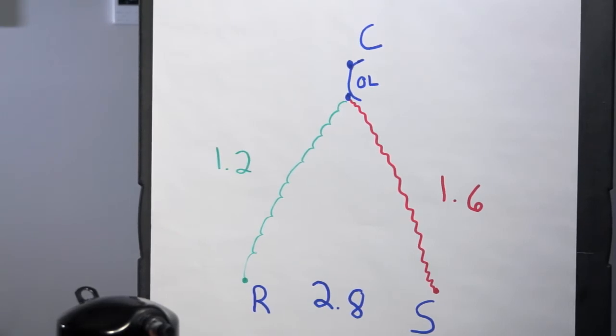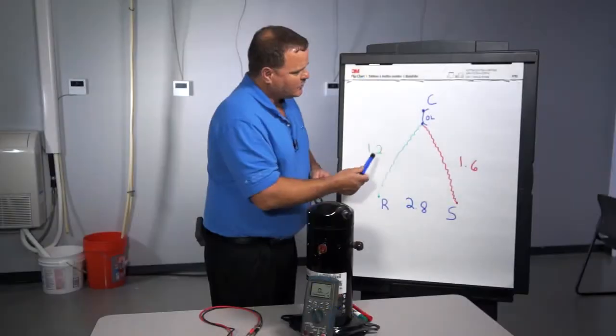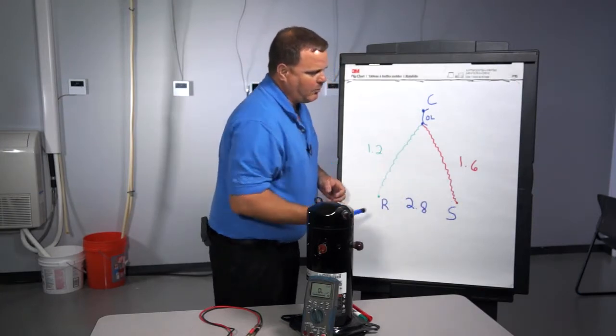from common to run, I got 1.2 ohms. Between common and start, I got 1.6 ohms.